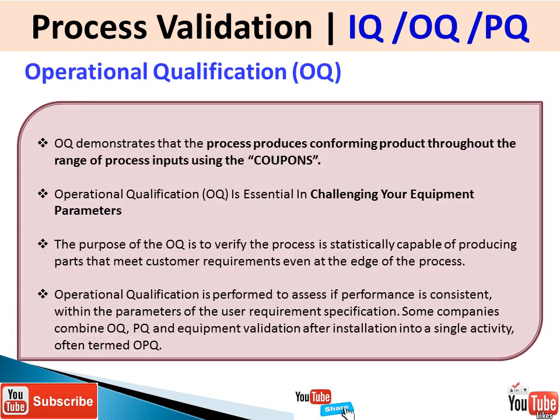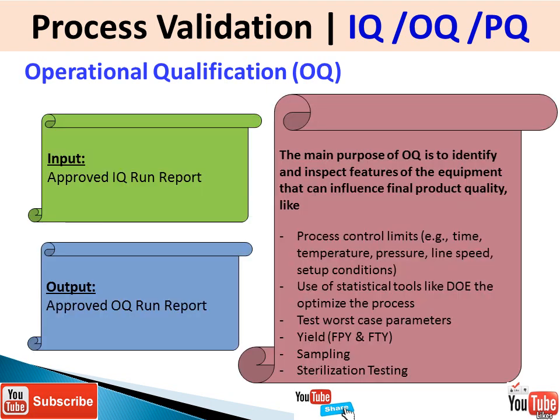Once installation is established, the next step is operation qualification. OQ demonstrates that the process produces conforming products throughout the range of different process inputs. You vary input parameters like temperature and pressure settings to determine where the best results are obtained. The main purpose of OQ is to verify that the process is statistically capable of producing parts that meet customer requirements even at the edge of the process.